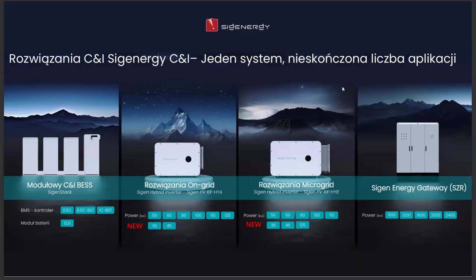For you, as installers and consultants, this is a very strong commercial argument. Instead of building large, expensive storage systems only to handle short-term power spikes, you can propose a compact, fast response, precisely sized solution that delivers exactly the power it declares, does not require oversizing, and generates real savings for the customer. This is exactly our philosophy: less is more, if the system is designed correctly.